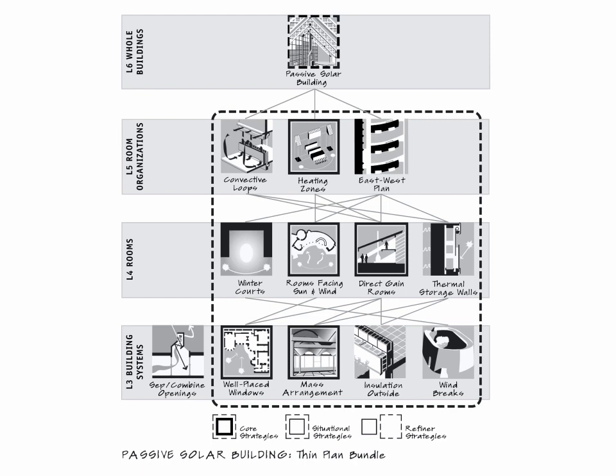In all buildings that need heat, you could use heating zones. All buildings using heat from the sun need rooms facing the sun. Direct gain rooms will work in both thin and thick plan but best for rooms that actually face the sun. You always need some thermal storage, so mass arrangement strategy is really important. Well-placed windows means orienting window amounts so you're increasing windows on the collection side, while other sides have enough daylight without overheating on east and west in summer or creating too much heat loss on the north in winter.